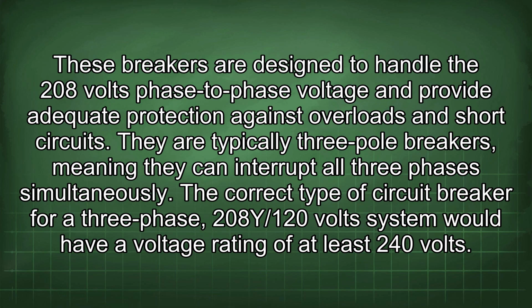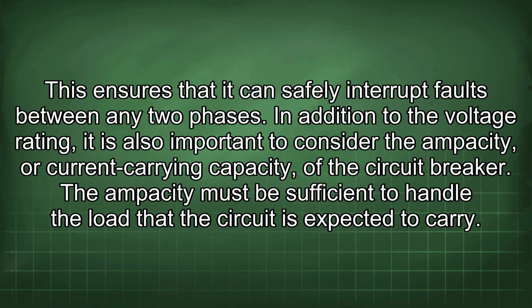The correct type of circuit breaker for a 3-phase 208Y/120 volts system would have a voltage rating of at least 240 volts. This ensures that it can safely interrupt faults between any two phases. In addition to the voltage rating, it is also important to consider the ampacity or current carrying capacity of the circuit breaker. The ampacity must be sufficient to handle the load that the circuit is expected to carry.